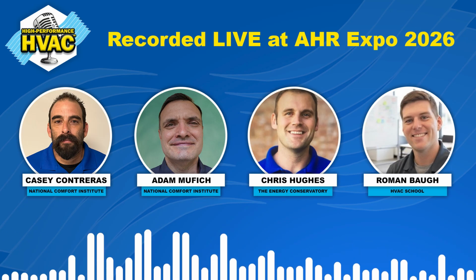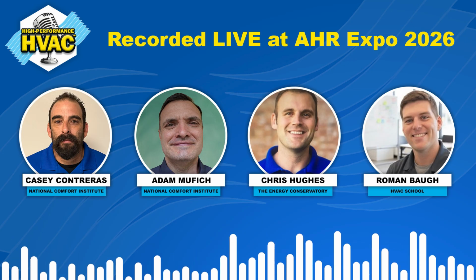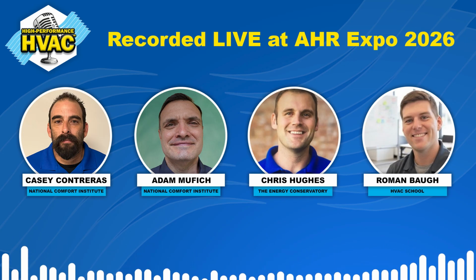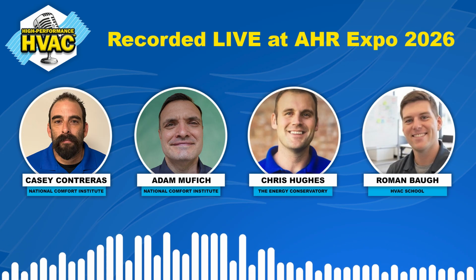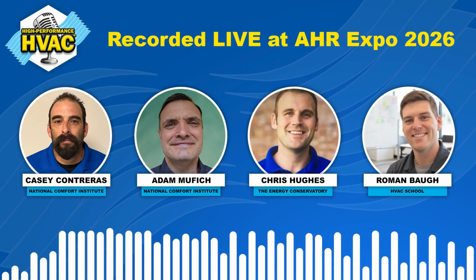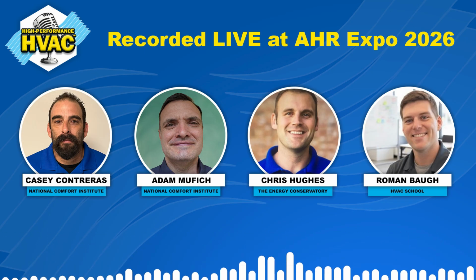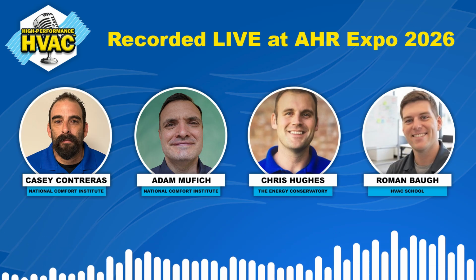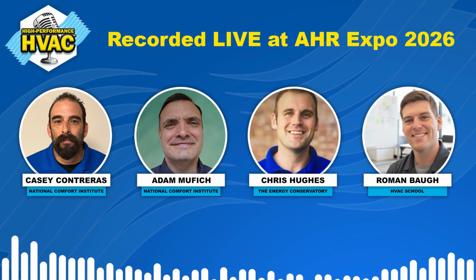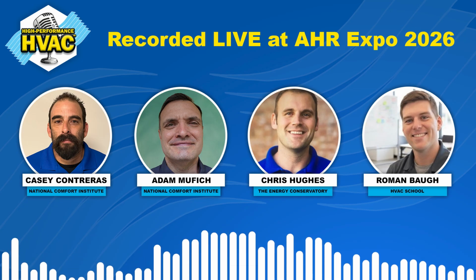Again, there is no right number. Every system is installed differently. Airflow's different. All these things add up, right? So you can't just say it's always got to be 68. And it's like, no, the real world isn't like that. We have to have a buffer zone because everybody's piece of equipment is different. But I like to see around there. We never want to see it on the high end. We never want to see it on the low end.